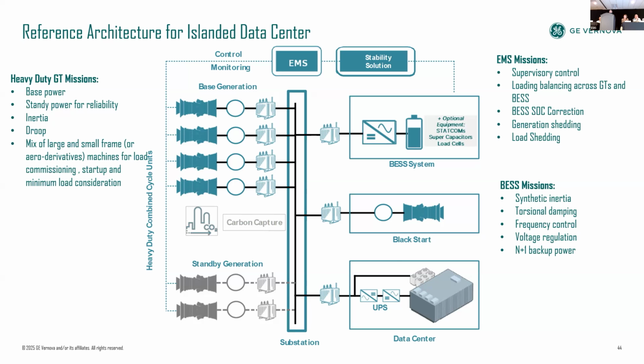So in this context, we are talking about energy storage systems which are grid forming, and I think previously there were some discussions regarding grid forming versus grid following and what is best for the system. These applications rely on grid forming because it allows the synchronous system to provide some relief to the inertial response and minimizes the overall size of the BESS, right?